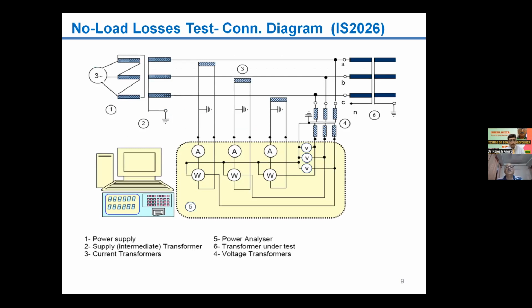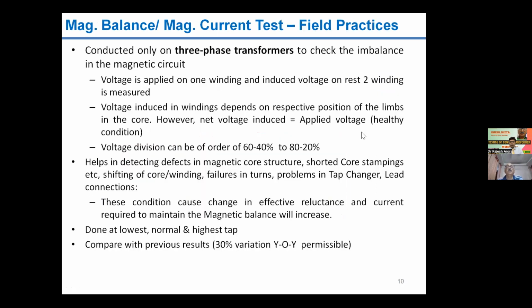It is the connection diagram. As you see, the equipment is connected in a circuit to measure no load losses. The specimen power transformer is indicated by 6, and the testing equipment is indicated by 5. The CT and PT connections are also indicated, and the source is 3. Source, current transformers, power supply, and like that we connect the supply, transformer and testing equipment. Next slide.